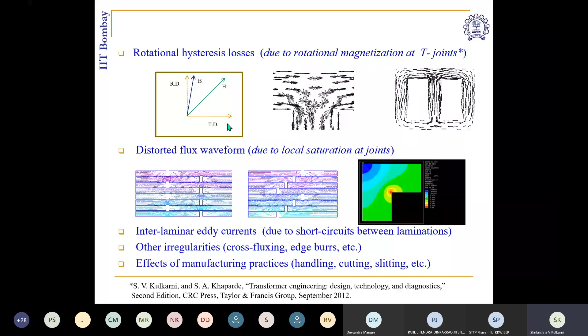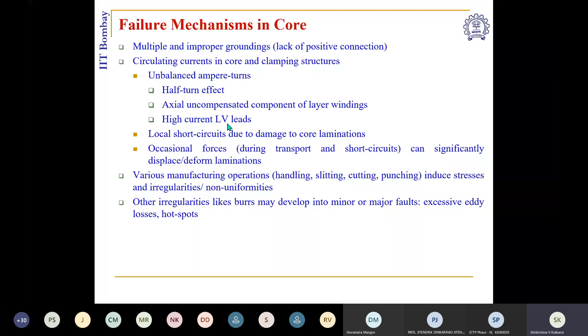Then you have various other irregularities in the core, like interlaminar eddy currents due to short circuit between laminations, other irregularities due to cross fluxing and burrs, and then the effect of manufacturing practices. The more you handle core laminations, the more you introduce mechanical stresses, and the performance of the core will further deteriorate. So there are various failure mechanisms in the magnetic circuit, like multiple or improper groundings, circulating currents in core and clamping structures, unbalanced ampere turns due to various phenomena like the half-turn effect, uncompensated components in the windings, or high current LV leads, local short circuit due to damage to core laminations, forces, and other things which I have already discussed.